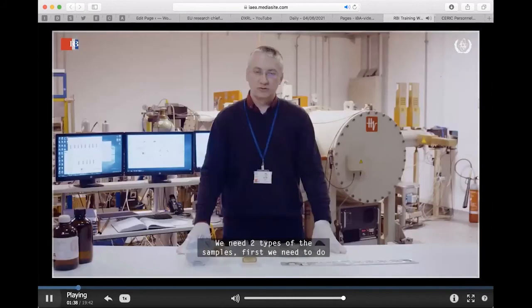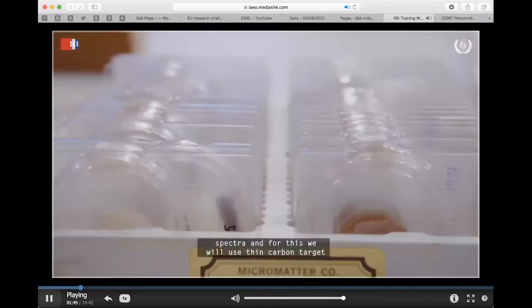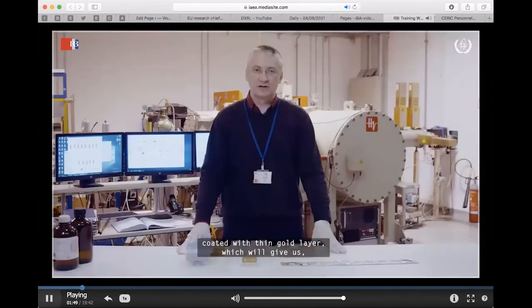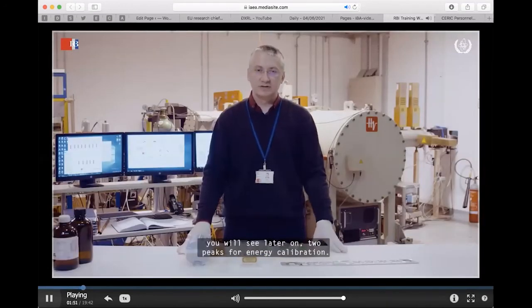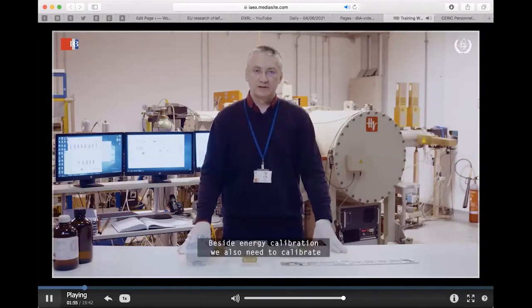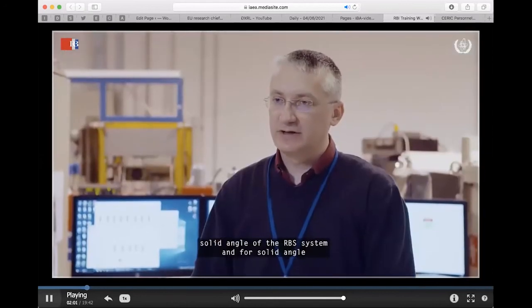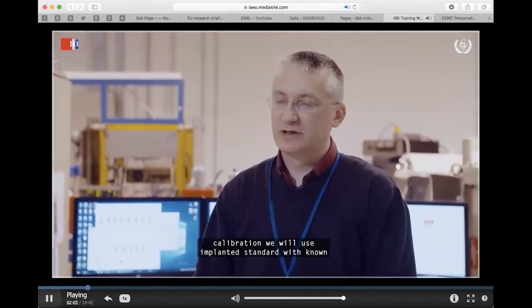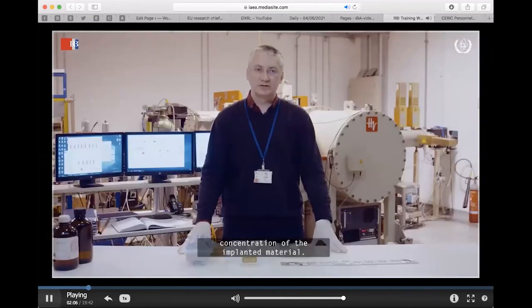First, we need to do energy calibration of the Rutherford backscattering spectra, and for this we will use a thin carbon target coated with a thin gold layer, which will give us, you will see later on, two peaks for the energy calibration. Besides the energy calibration, we also need to calibrate the solid angle of the RBS system, and for this we will use implanted standards with known concentration of the implanted material.